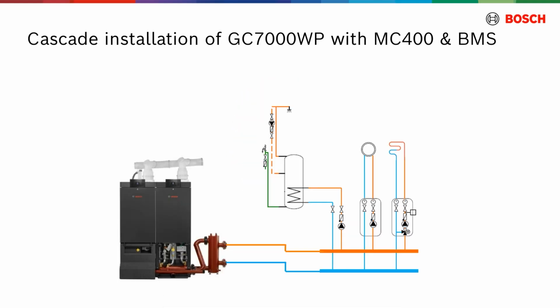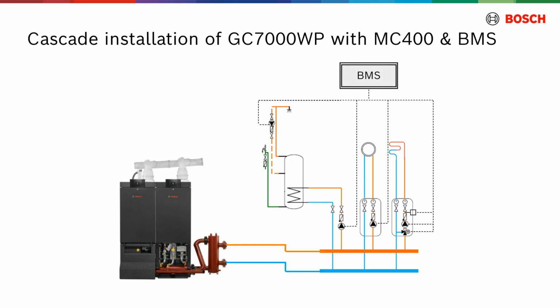When integrating with an existing building management system, BMS, one of the possible solutions is the use of the MC400 module. This module facilitates the seamless integration of a cascade setup of Bosch condensing boilers. It controls the heat output or temperature demand of the GC7000WP cascade by converting the 0 to 10 volt output signal from the BMS. This solution requires no programming or complex setup, offering a straightforward plug-and-play experience.